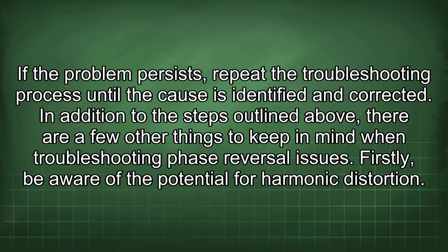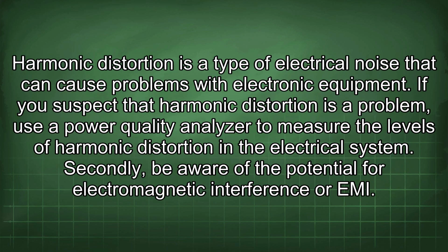In addition to the steps outlined above, there are a few other things to keep in mind when troubleshooting phase reversal issues. Firstly, be aware of the potential for harmonic distortion. Harmonic distortion is a type of electrical noise that can cause problems with electronic equipment. If you suspect that harmonic distortion is a problem, use a power quality analyzer to measure the levels of harmonic distortion in the electrical system.